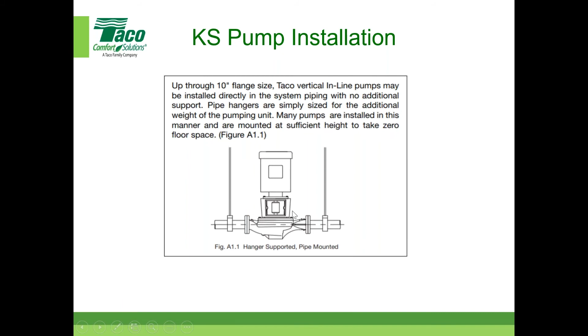I have seen people support them like this, free, up to 10-inch flange size. You can install them directly in the piping system with no additional supports, as long as the hangers are sized correctly. And then here are some other pictures for 15 and below, up in the ceiling or up off the floor, with all the piping systems there. You can see the different arrangements, and it's not unusual, right? The suction diffuser attached right to the suction side here.